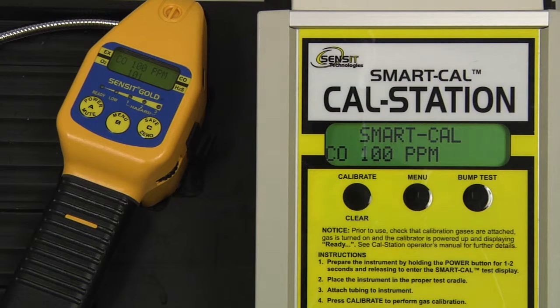In this case, because the selected gas type of the Gold 100 is propane, the first calibration gas in the sequence is 100 parts per million CO. Once a stable reading has been achieved, data saved will be displayed on the screen of the instrument, and passed will be displayed on the cal station. The number on the display of the instrument is the raw output of the sensor, and is useful as a reference when troubleshooting if any issues should occur.